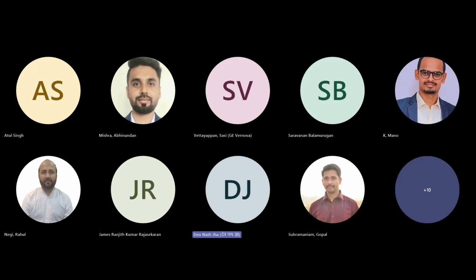So we are still working on the complete development of digital twins. Like I said, we have only created the health model, the failure model, the impact model, and the aging model. The tools we used: for the health model, we used AI/ML models of random forest along with ensembles, that is AdaBoost. The aging model was empirical-based modeling, so no particular software was used for that. While creating the failure models, we used NLP to extract the relevant values from the design documents and then populated the data in an Excel sheet, and that data was further correlated with dielectric failure history.